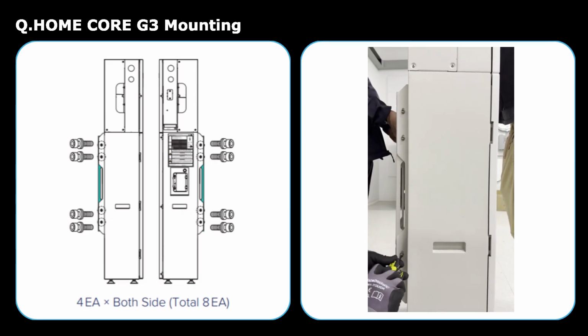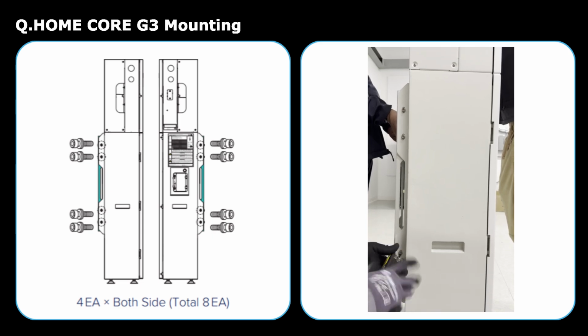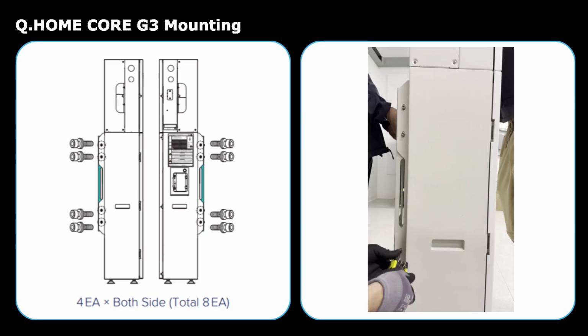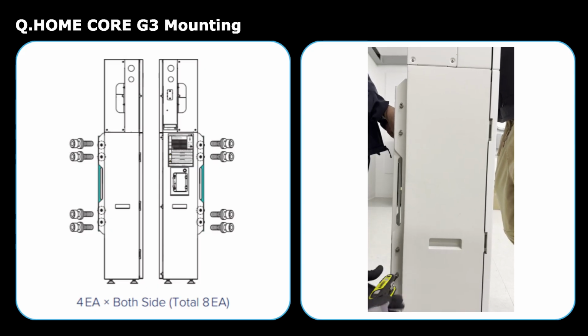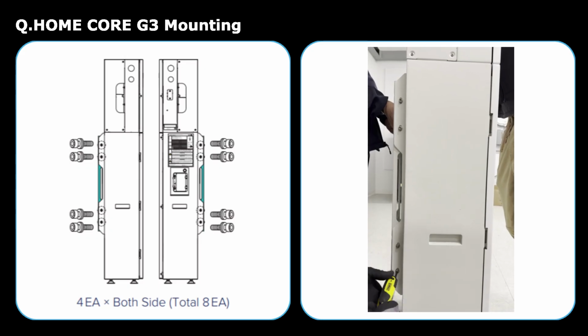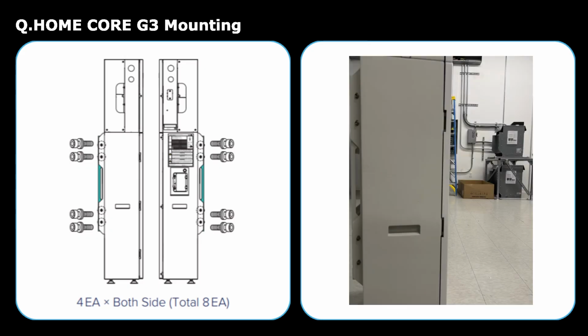Finally, adjust the leveling feet at the base of the system until it is completely stable and flush with the floor. For safety, always use 2 people when lifting system components. Also, fully install the enclosure first before inserting batteries.